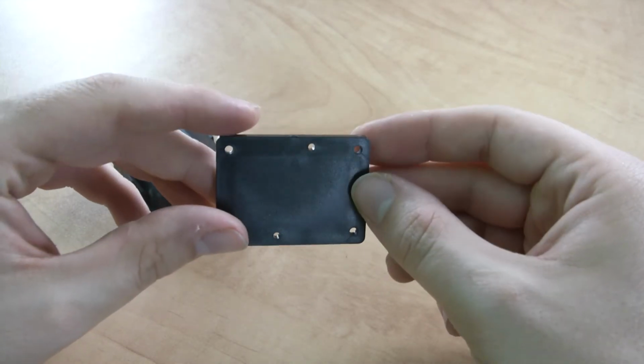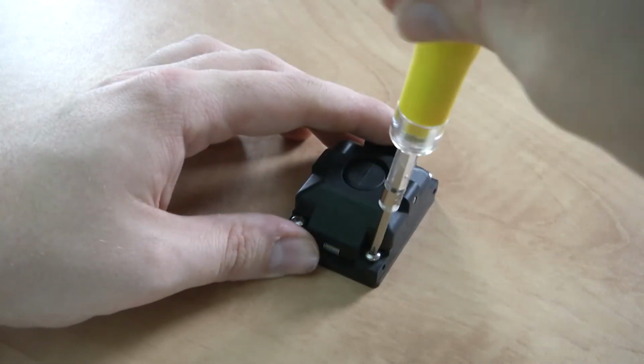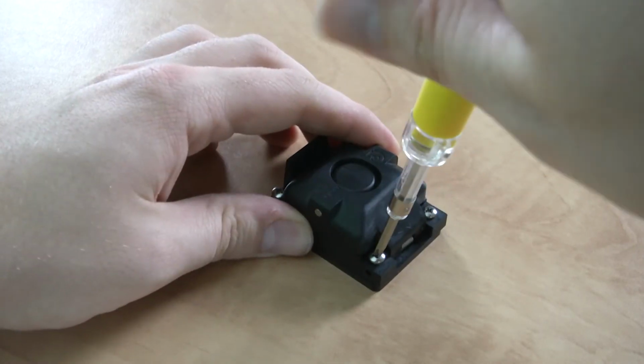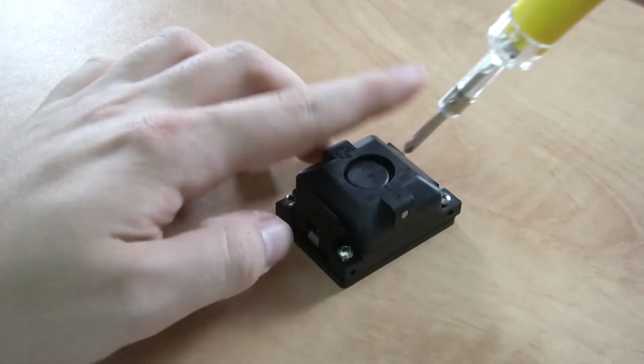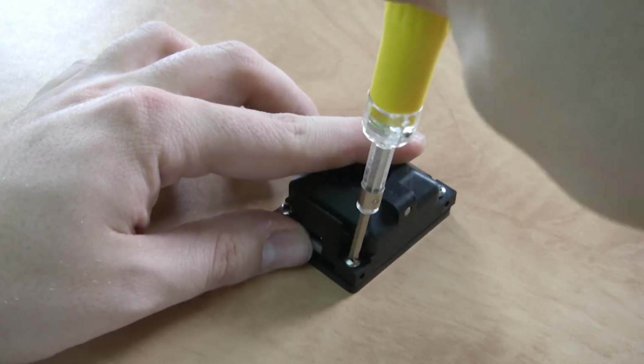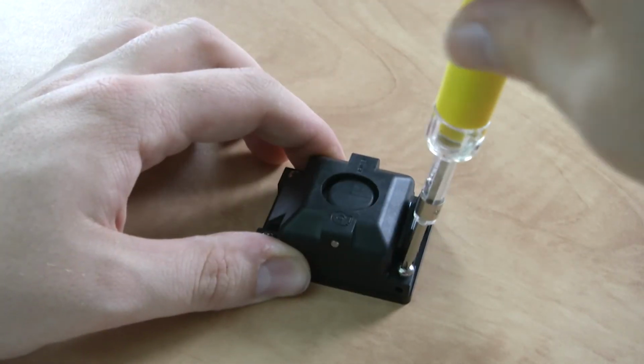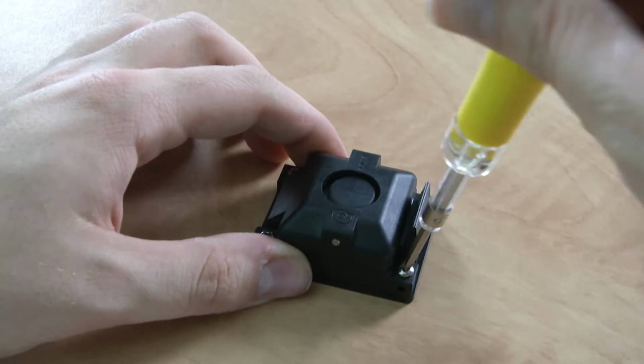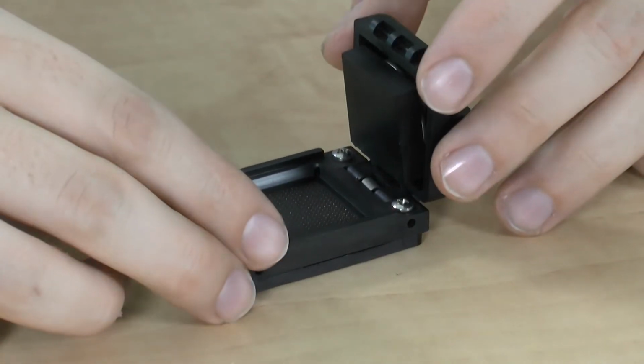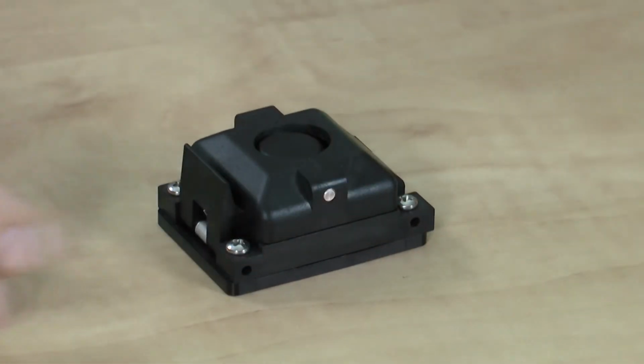Hold the socket so the bottom is parallel to the test board and slowly lower the socket alignment pins into the alignment holes and bolt the socket to the test board. The bolting process compresses the bottom coils of the spring probe springs that extend past the bottom surface of the interposer to mate with the pads of the customer's test board, creating a pressure mount.